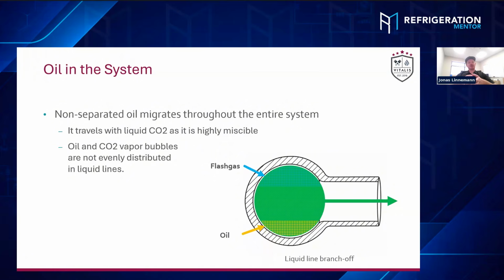As soon as you have the vapor traveling through the vapor lines and you maintain the required velocities, you would still carry those oils back. You just have, as I've mentioned as well, a lower amount of CO2 solved inside the PAG oil. So especially for low temp applications, the oil is just thicker because there's such a low amount of CO2 inside. And CO2 at that point solves the oil to a more thin liquid, and that is beneficial for the oil return.